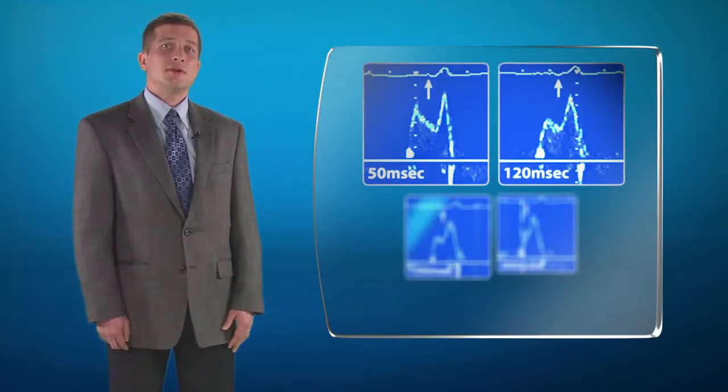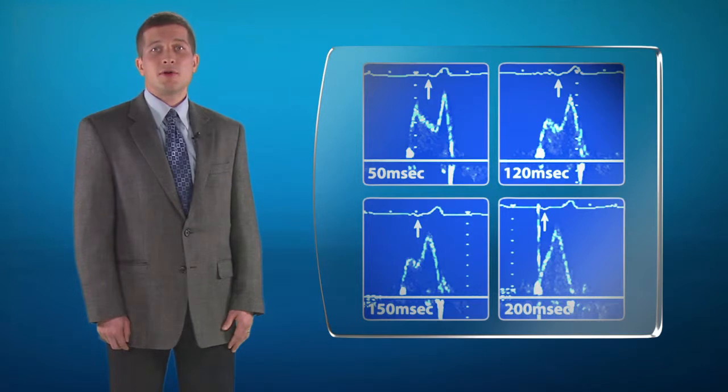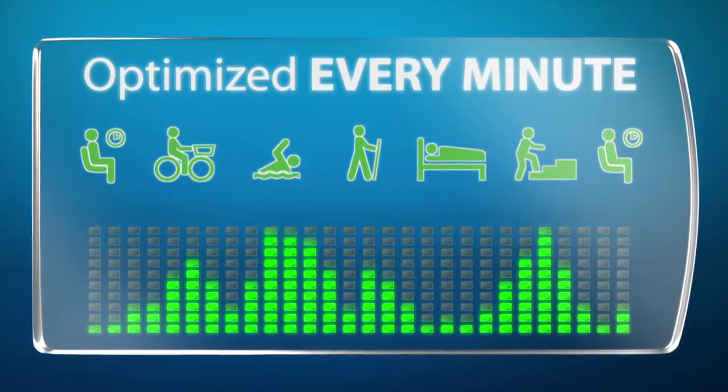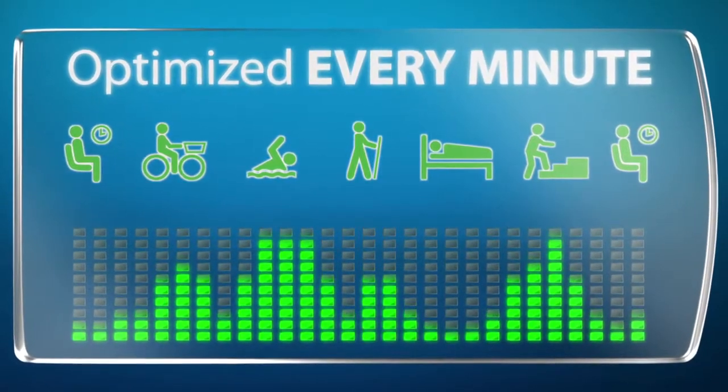Cardiac resynchronization therapy systems are designed to manage ventricular conduction delays in patients with cardiac rhythm disorders. Each patient's conduction problem, however, is unique, and ideally parameter settings should be optimized for each patient. To date, CRT optimization has been a time-consuming, manual trial-and-error process requiring ultrasound evaluations. In addition, settings may need adjustment if the patient's activity level or condition changes.